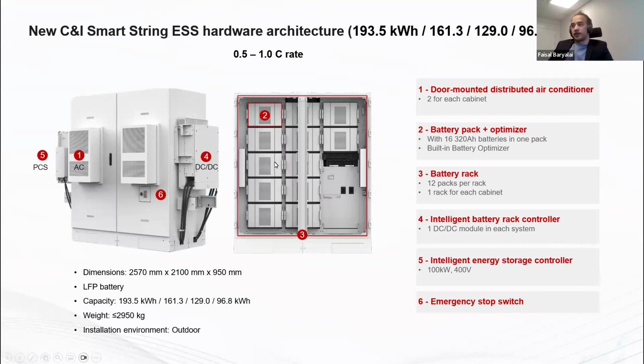Inside the cabinet we have the storage itself, the modules, which store energy - approximately 16 kilowatt-hours per module. In one cabinet, at maximum, we can have 12 of these modules. These modules should be assembled after we put the container on the foundation at the customer site. There are also a lot of communication lines between the modules, and copper bars between the modules - all these should be assembled at the last stage once the modules are inserted inside the battery.